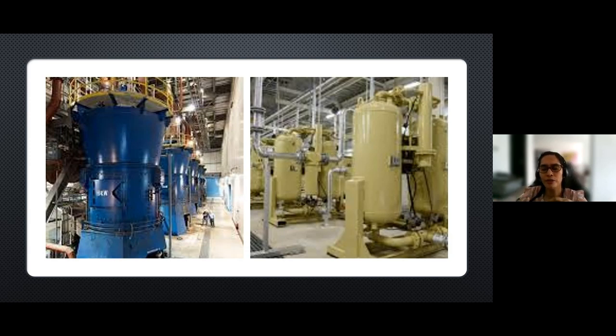Something that we have to realize as well is the need to implement ways to control the auxiliary power consumption. And something that we realize is the consumption of power of the compressor systems. Once we evaluate, we realize that according with the manufacturer conditions, we should operate with 7 compressors, but actually we were working with 8 compressors. So we have to study what happened in the compressors, do a performance test, and realize that we should decrease the use of 1 compressor to go to 7 compressors and reduce the power consumption.